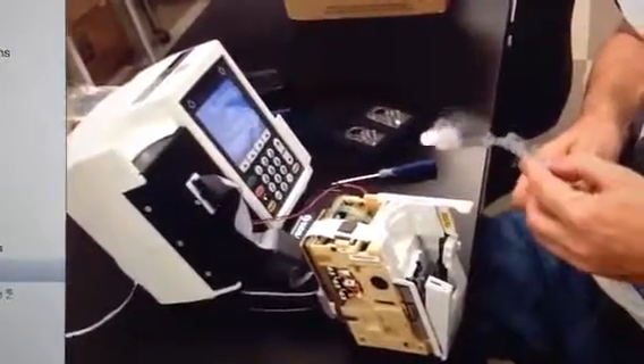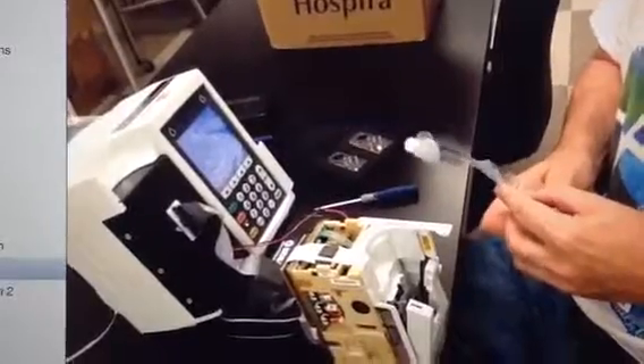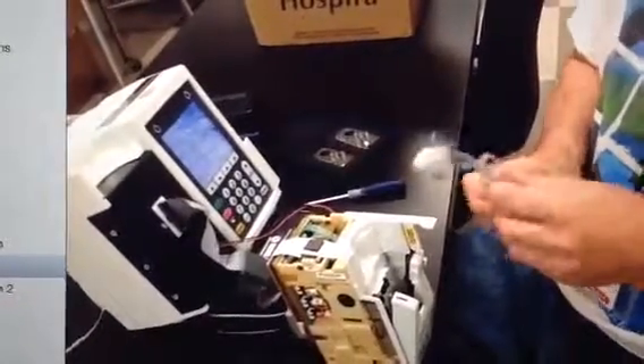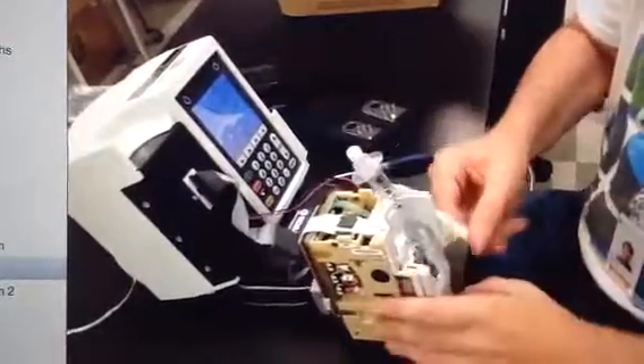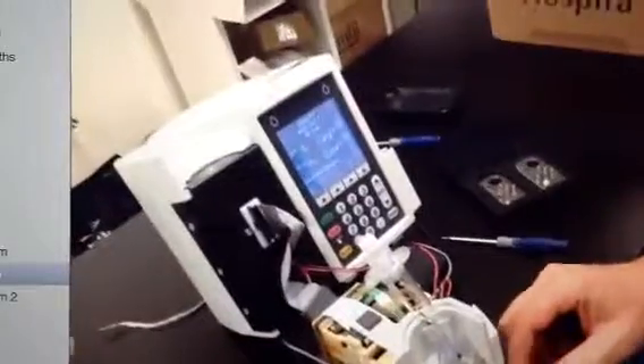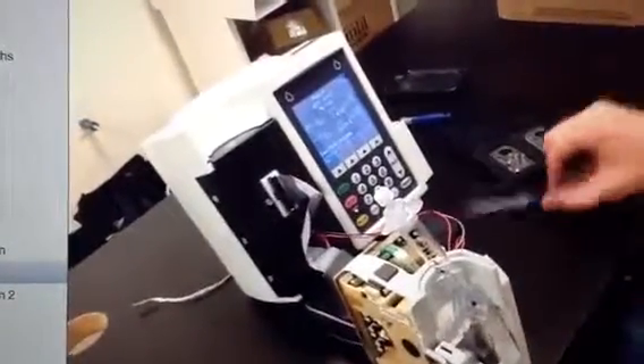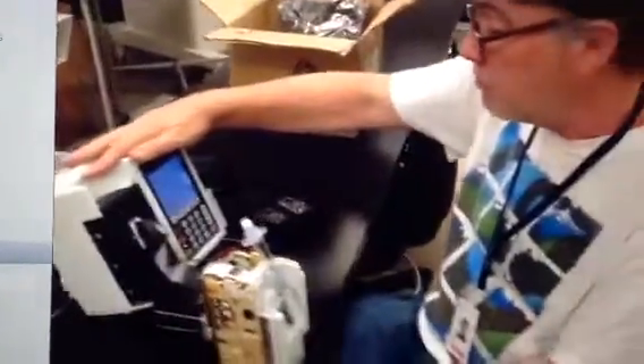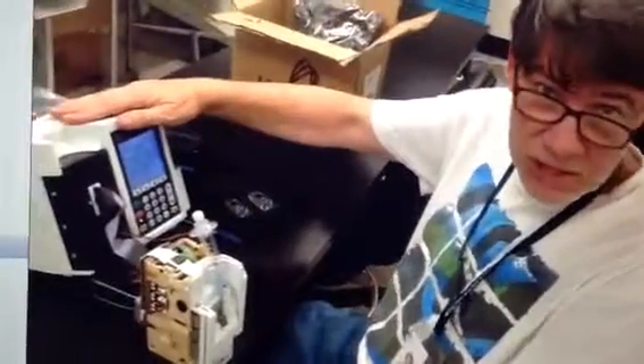We're going to be able to calibrate the proximal air. Yeah, the proximal air we can't calibrate with this cassette. But this pot right next to it, right here, is used for the proximal air. And we would turn that, and we would eventually get to between 1400 and 1500 on proximal. We hit set, and it says malfunction, proximal fluid too low. That's because we couldn't calibrate that. So the fixture itself tells you whether you successfully calibrated the device or you did not.